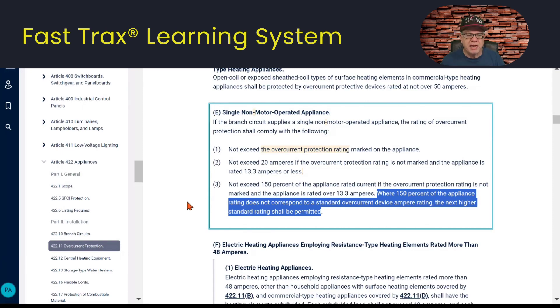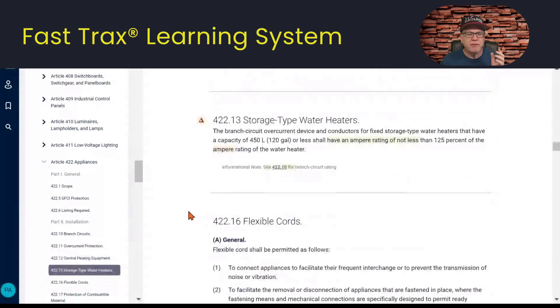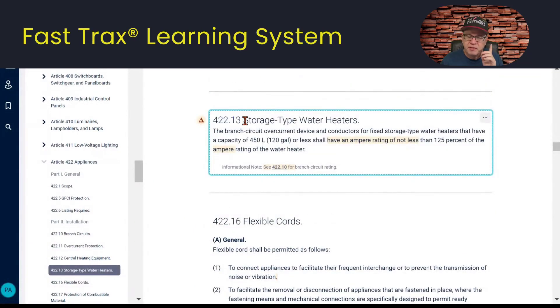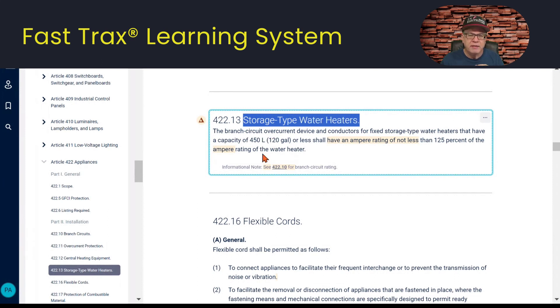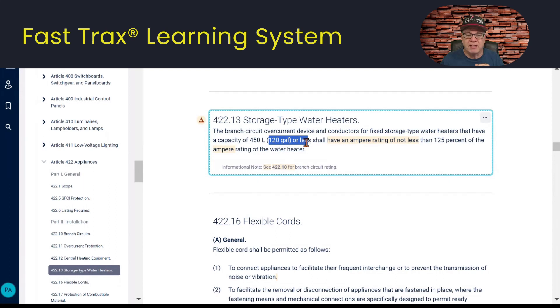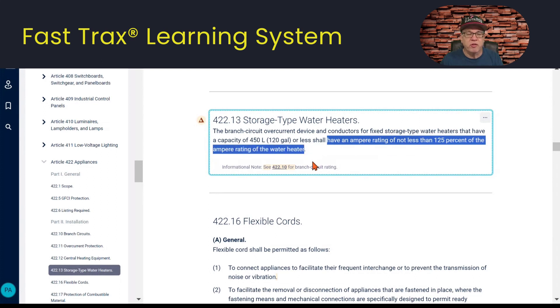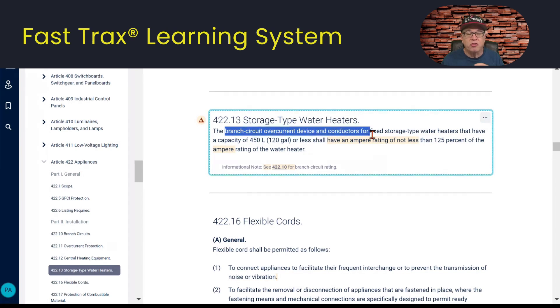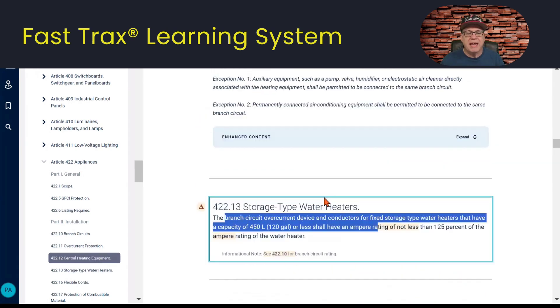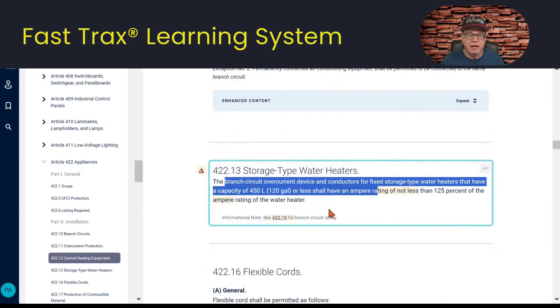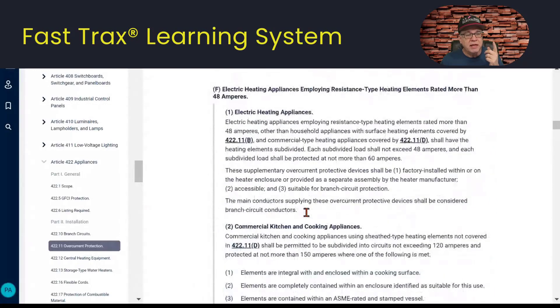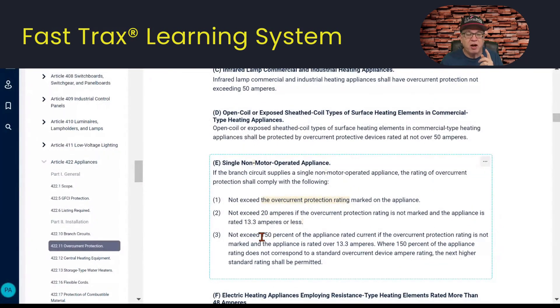The other rule folks look at is 422.13, which specifically covers storage-type water heaters with a capacity of 120 gallons or less. It says the ampere rating shall be not less than 125% of the ampere rating of the water heater. So that's a minimum — the branch circuit overcurrent device and conductor cannot be less than 125% of the water heater's ampere rating. The rule in 422.11(E)(3) is a maximum not to exceed 150%, while 422.13 sets the minimum at 125%.